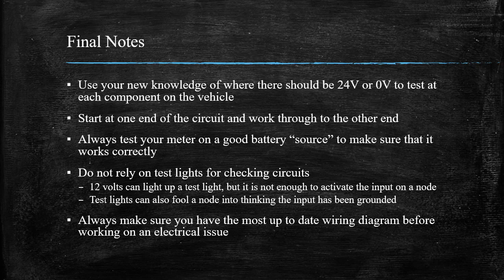Always test your meter on a good battery source to make sure it works correctly. I've had many times where you're using a multimeter and get readings that don't look correct, and you assume the problem is with the vehicle, but the problem is really with the meter. So it's really important that you test your meter, confirm on the battery it's actually functioning correctly, and that you didn't blow a fuse or something in the meter.